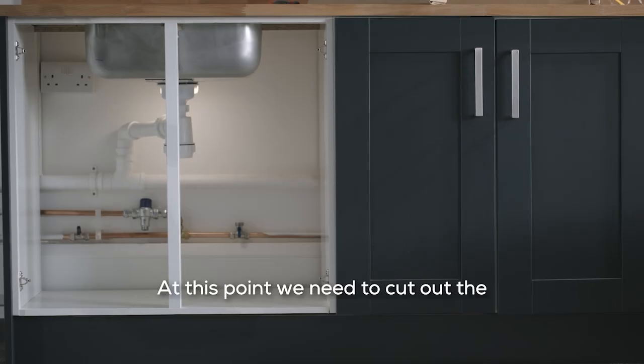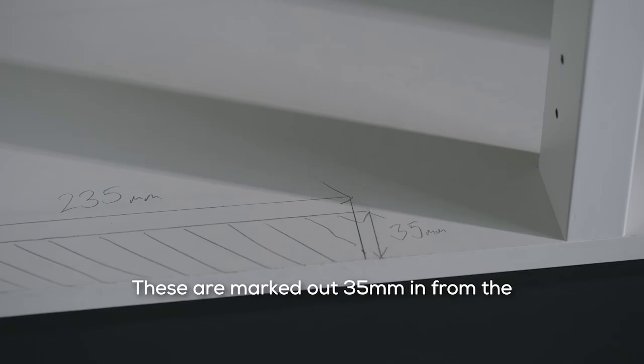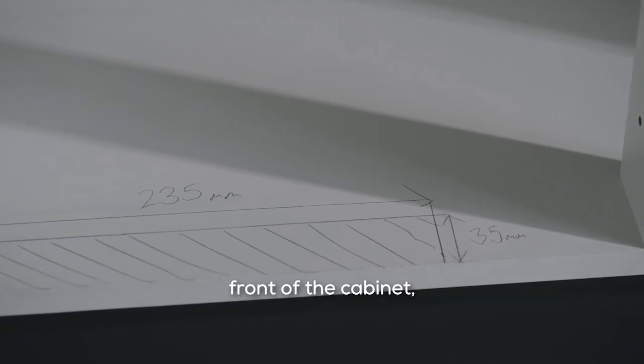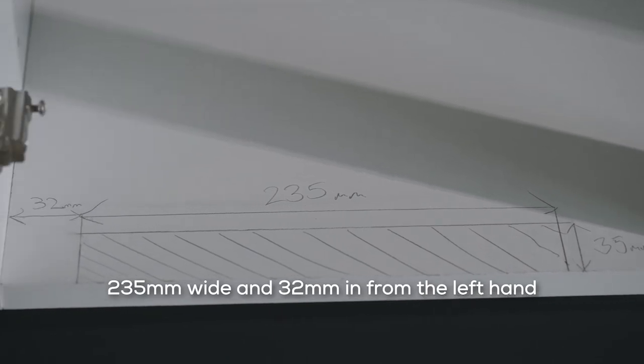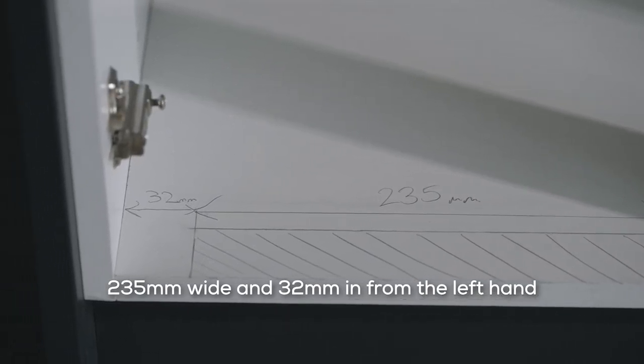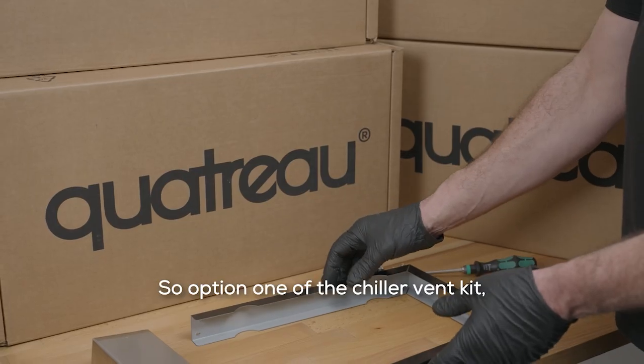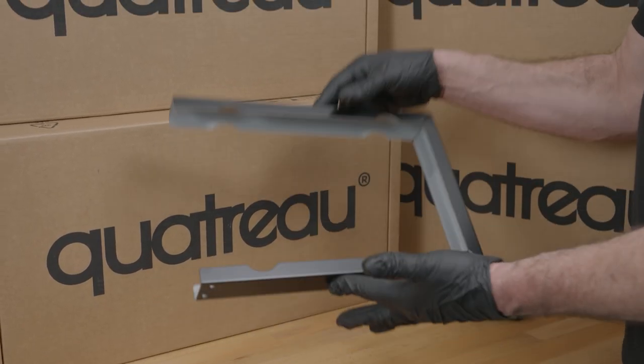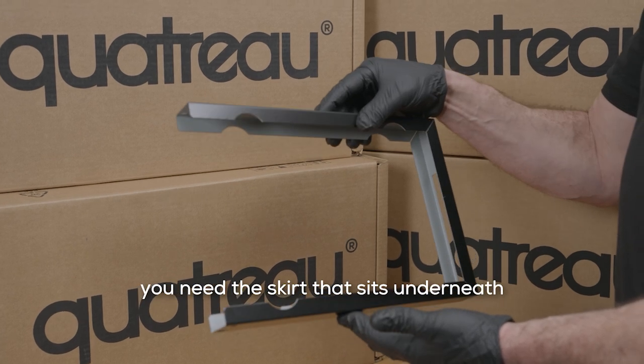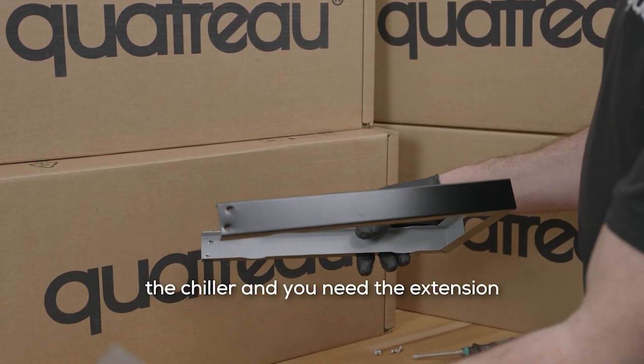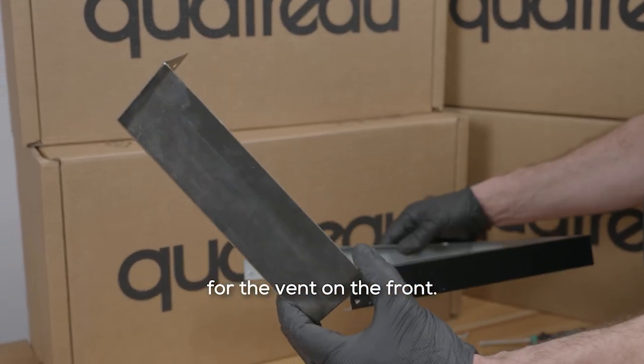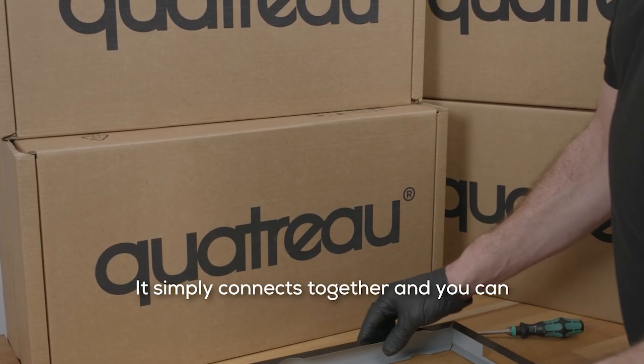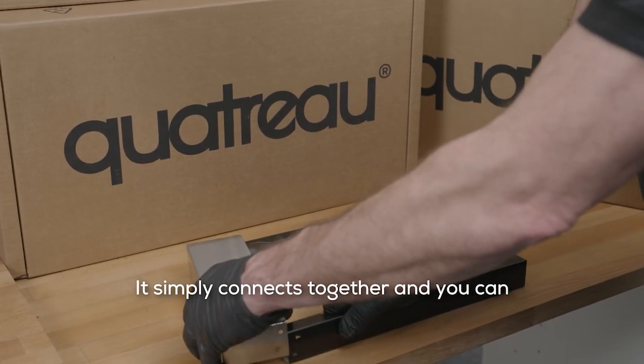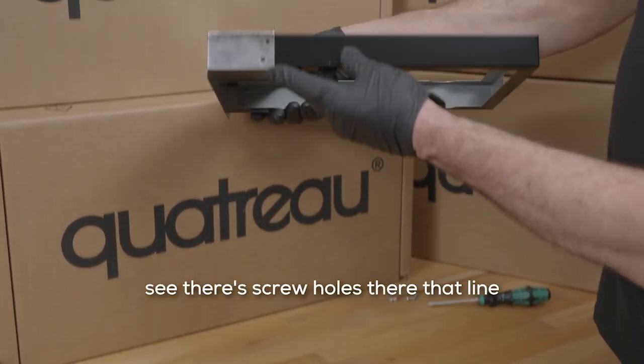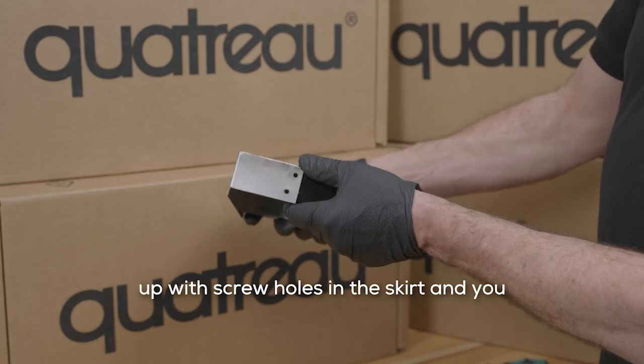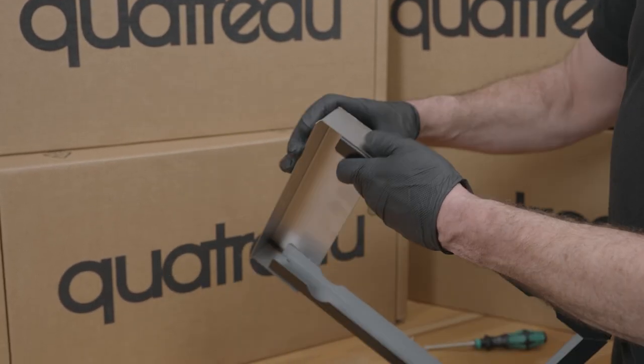At this point, we need to cut out the essential ventilation for the chiller. These are marked out 35mm in from the front of the cabinet, 235mm wide, and 32mm in from the left-hand side of the cabinet. So option one of the chiller vent kit: you need the skirt that sits underneath the chiller, and you need the extension for the vent on the front. It simply connects together, and you can see there's screw holes there that line up with screw holes in the skirt, and you get the screws provided.